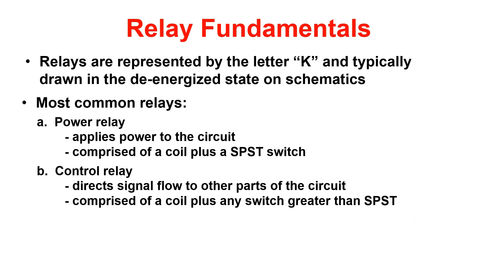The most common relays are the power relay and the control relay. A power relay is utilized to apply power to a circuit and is comprised of a coil and a single pole single throw switch. A control relay is utilized to direct signal flow to other parts of a circuit and is comprised of a coil plus any switch combination greater than a single pole single throw.